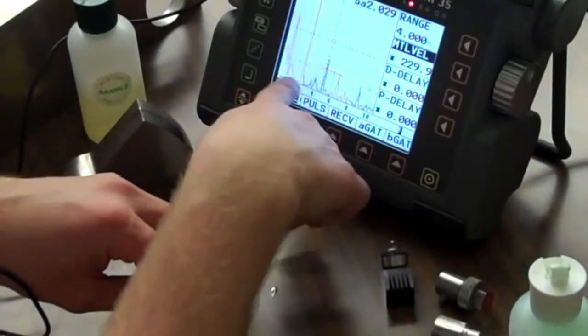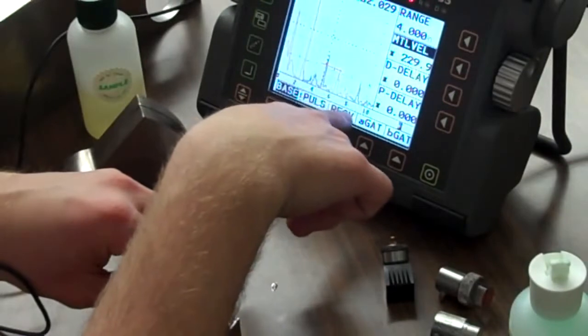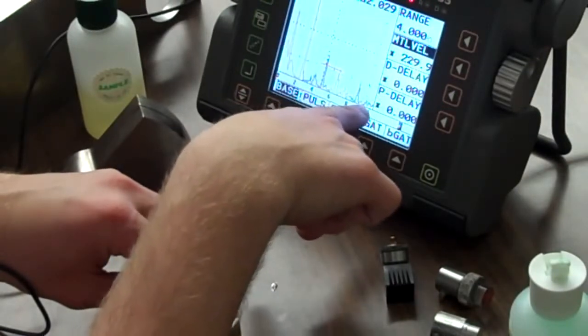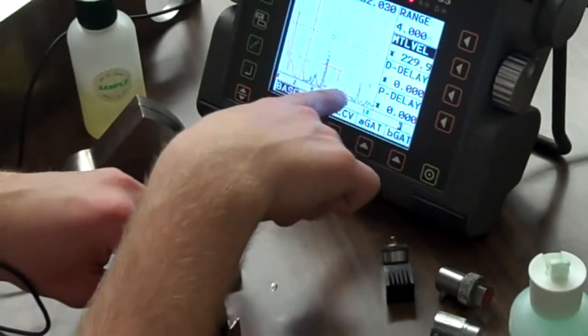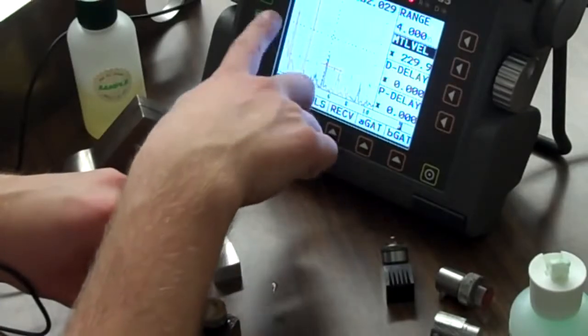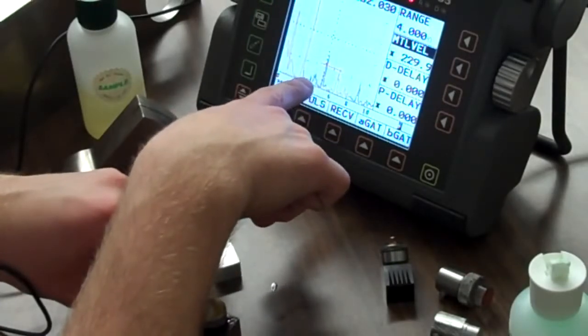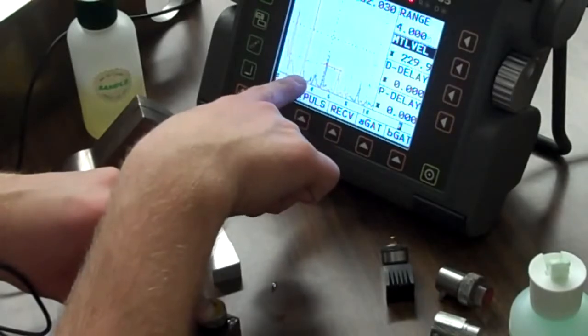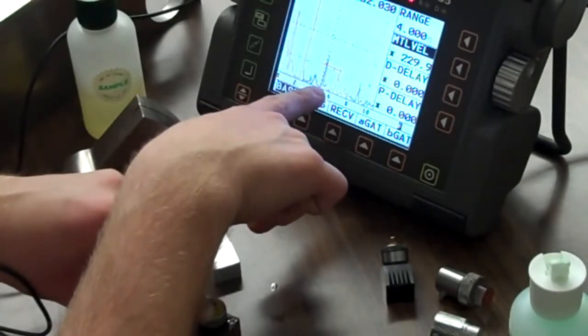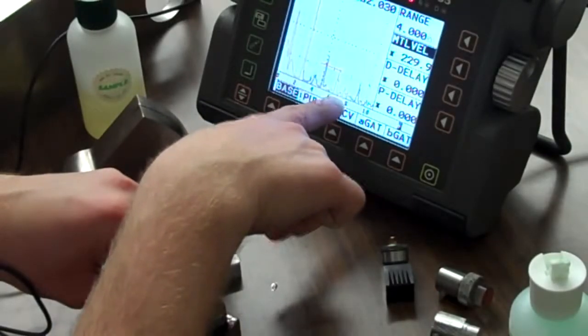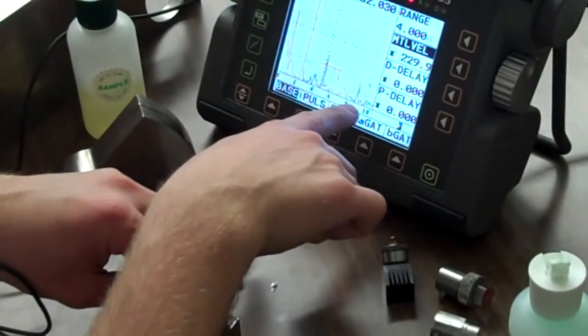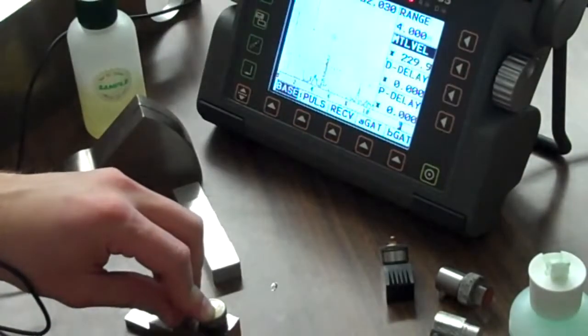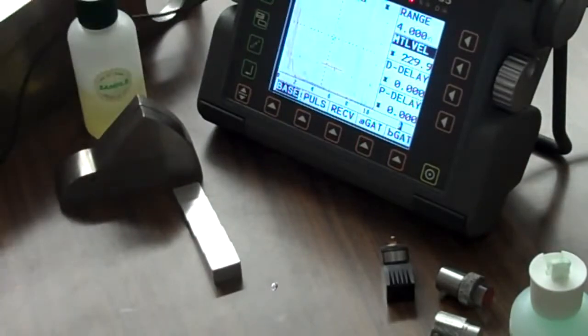Okay, so here's our 25, here's our 50, 75 is right here, and our 100 is pretty much burned up over here. This is kind of reflections inside the block, bouncing back from the near field, just some general junk. So at 25%, we're looking pretty close. At 50%, we're pretty much right on the money. At 75%, not so pretty. At 100%, not so pretty either. So let's go to a little prettier block.